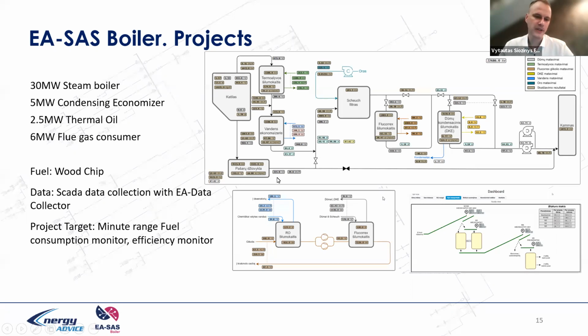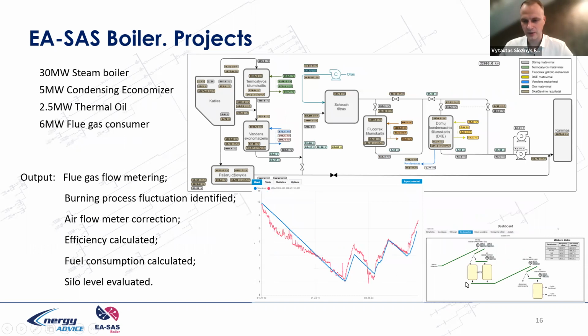So we calculate biomass fuel consumption by direct methods, from the burning process model and from the heat model of the process, from heat consumption metering results, temperatures, etc. So it is a full model of biomass burning, and we calculate fuel calorific value, water content in the fuel, and biomass fuel consumption. All these results were compared. We store biomass fuel in the silo. Here is the silo level: the red color is from metering, and the blue color is from the calculated value. The silo level was monitored, for example here, over 4 days, comparing the calculated and the metered value, and the biomass metering was made by direct methods.